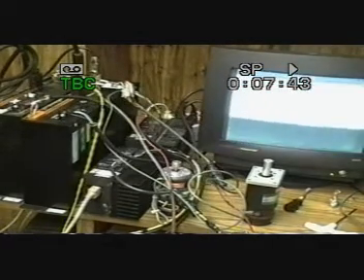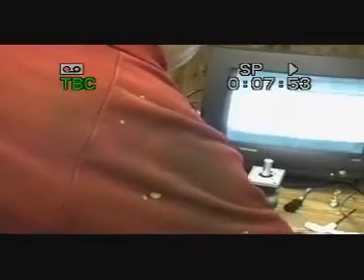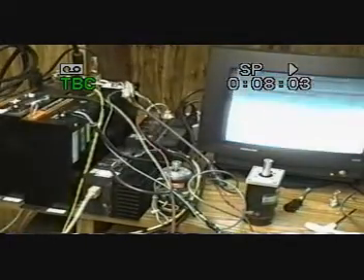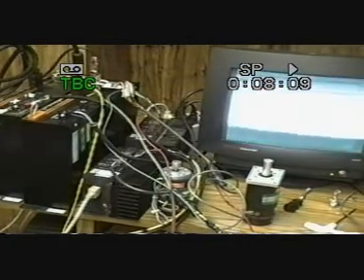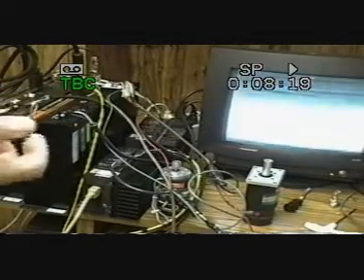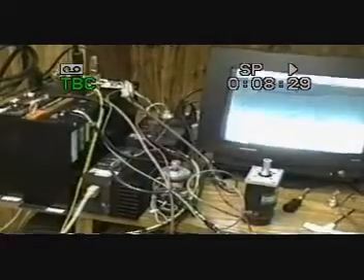Now another question that you may have come up with when you went through the software, you'll see, oh, I was getting encoder pulses in, why am I having a fault? If we do look at the diagnostics here on the encoder, even with an encoder fault, we will see on encoder 2 that pulses are coming in from the press. And that is correct, that they are coming in from the press. What we have is a hardware up-down chip, and that does count quadrature encoder pulses, but we have another circuit. It's not a software circuit that verifies encoder faults, and we've fallen below that level.